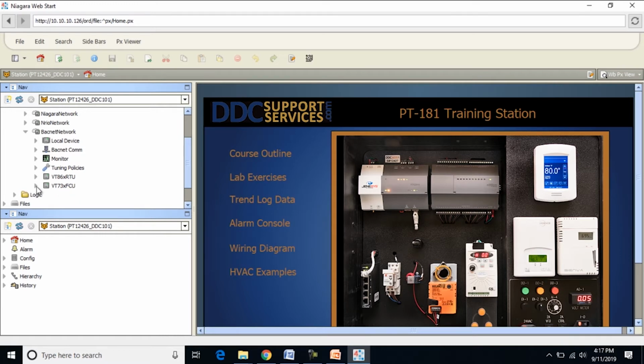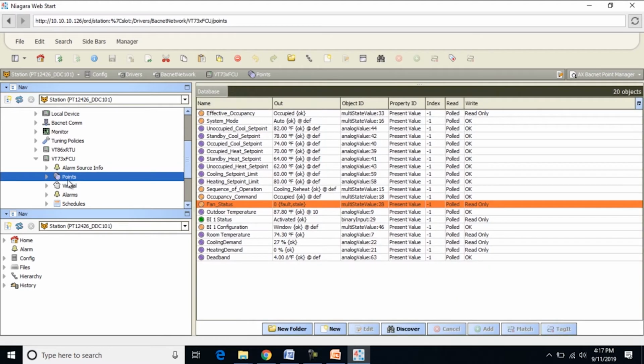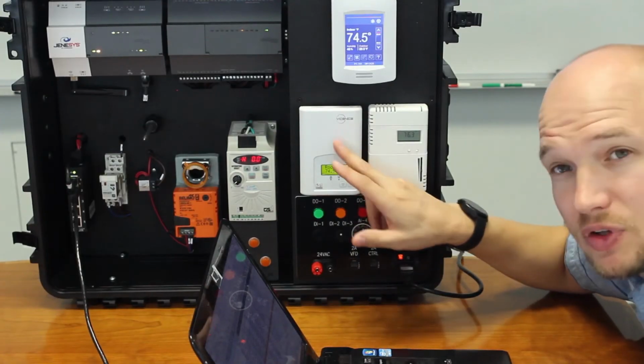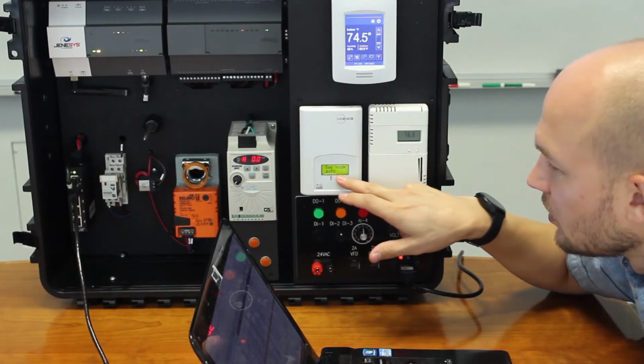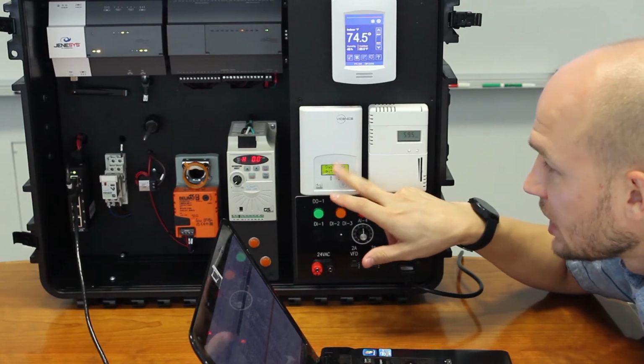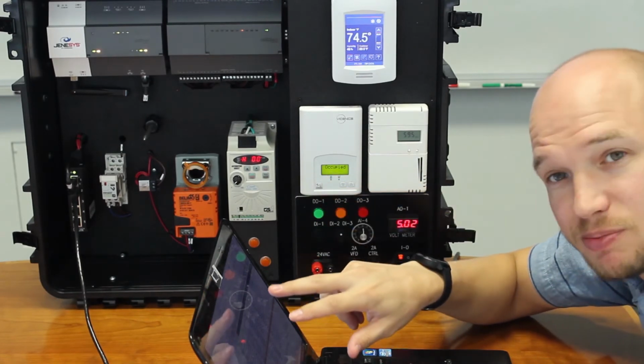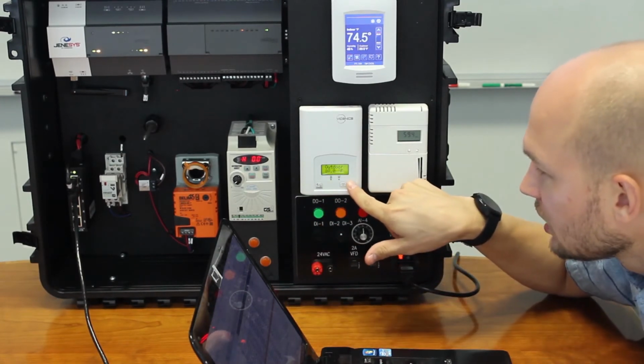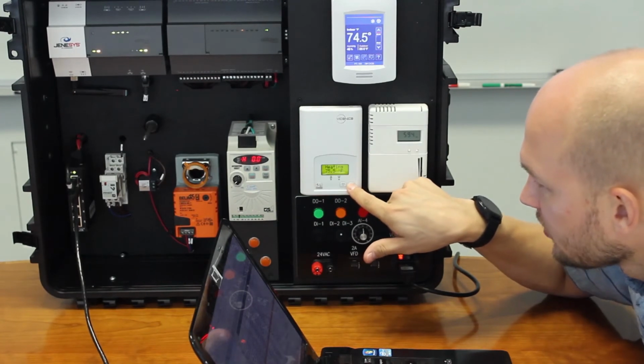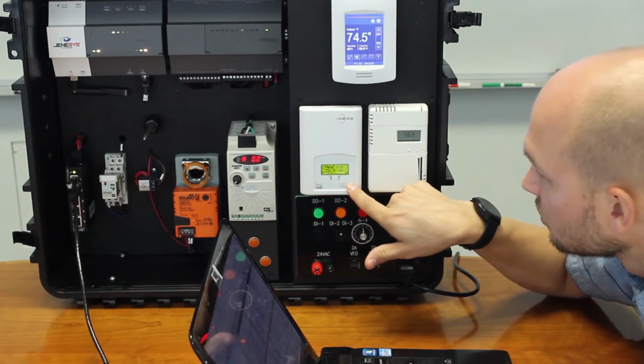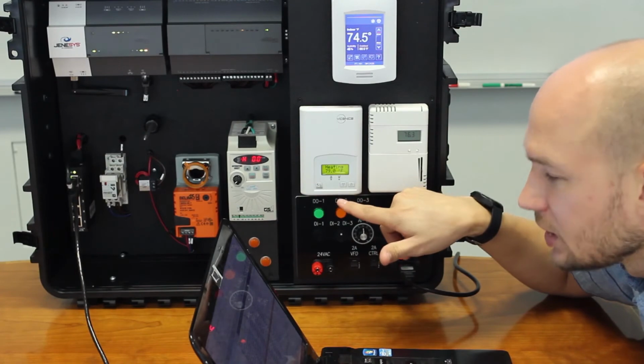So if we expand the fan coil unit controller and we look at the points here, you can see these are all the points that are communicating back and forth between the JACE. And so now if you look at the fan coil unit here, all the information that's displaying on the screen here is displaying on the computer. What I'm going to do here is I'm going to raise this temperature up. So we'll go to 79 degrees.